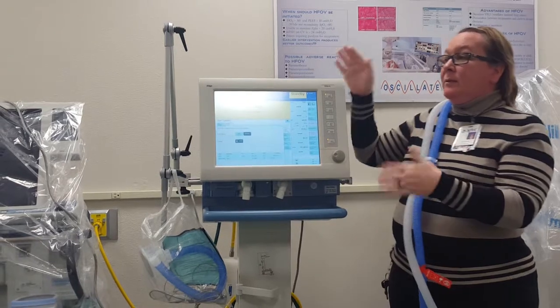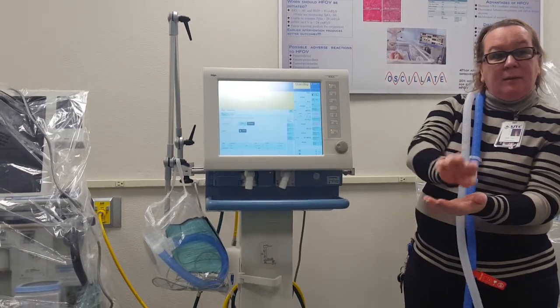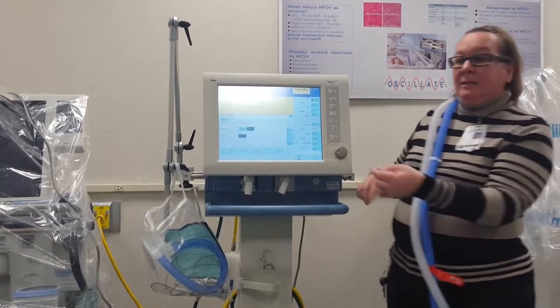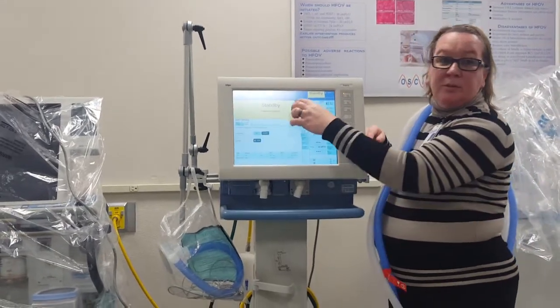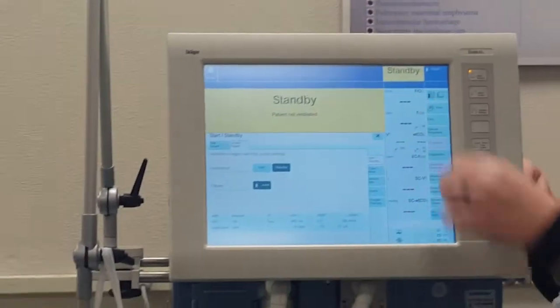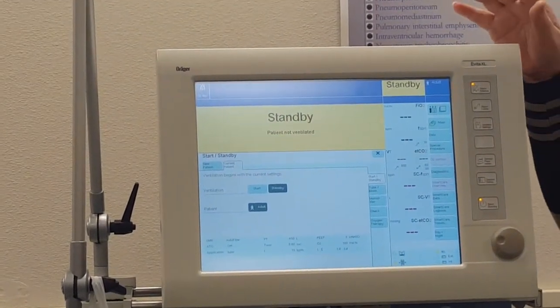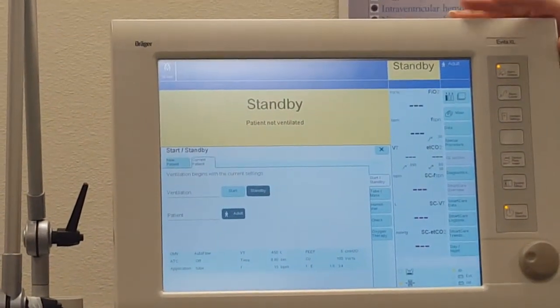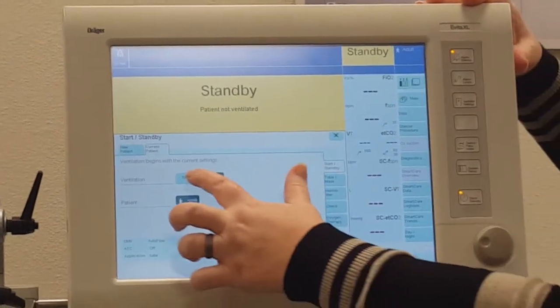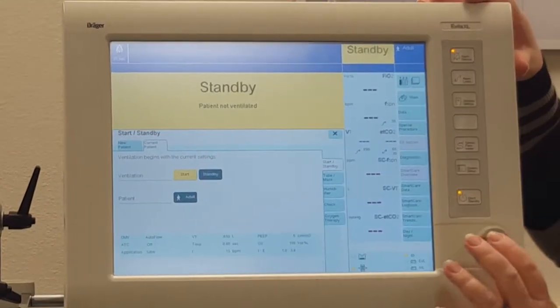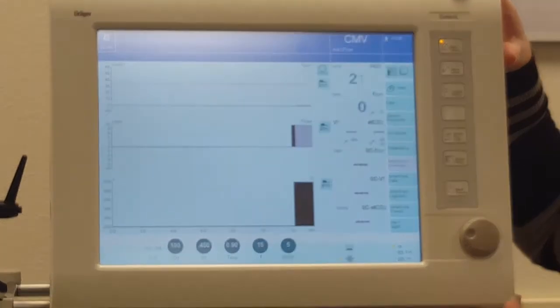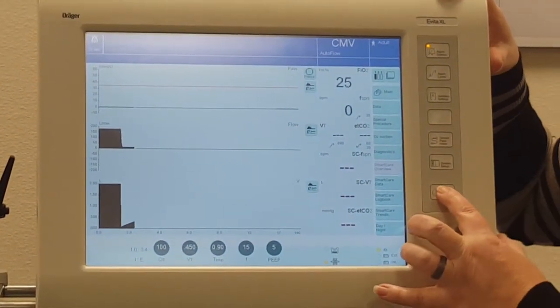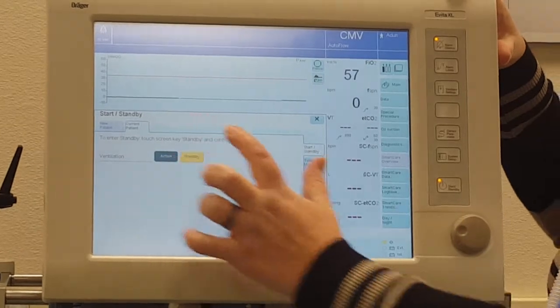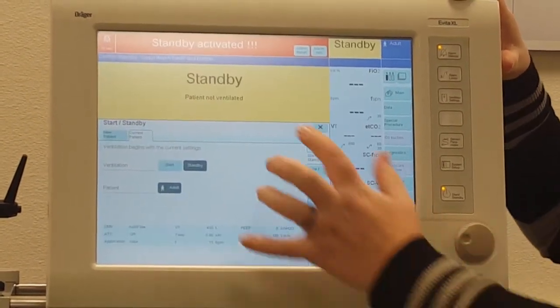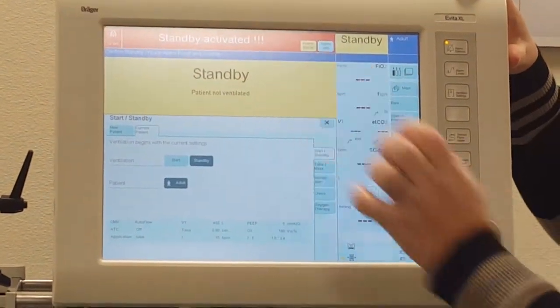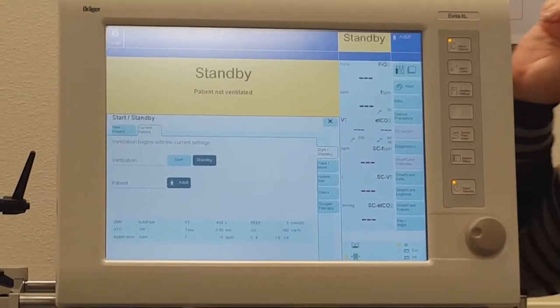Like the PB would put our stuff down at the bottom. If you hit the button and you see a little writing down at the bottom, the DRAGER puts its writing up here in the blue. So up here is where you'll always see your instructions that will tell you what to do. We'll just do it one more time and make sure everyone's got it. We're going to start ventilation, hit the word start, and ventilate. Now I want to go into standby: hit the start standby button, hit standby, confirm, which is the round button, touch alarm reset, and confirm. Now we're actually in standby.